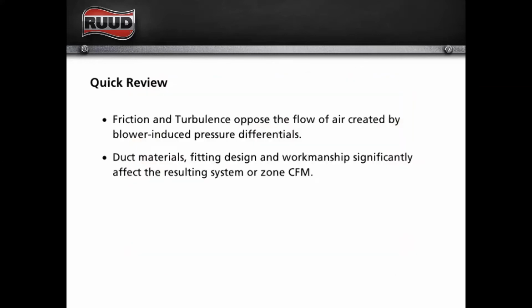So before we move on, friction and turbulence make it tougher for the air that we have to move, right? It's air conditioning. If we're not moving the air, we're not conditioning it. It's extremely important. And the materials that we use, the design and the workmanship of that ductwork has a huge effect on how much air we can actually move. So does it get more important than moving the right amount of air? And we have all the control over that.